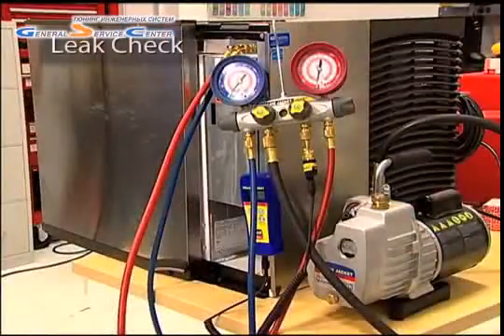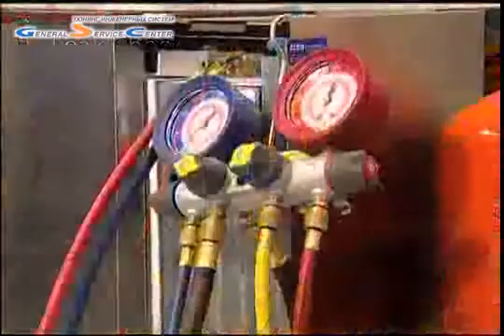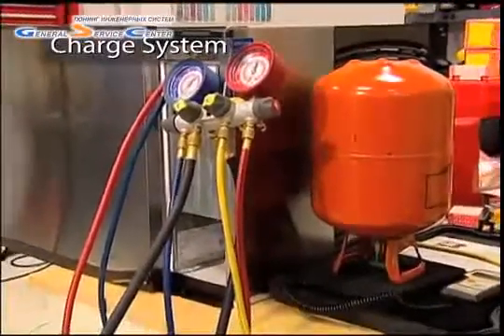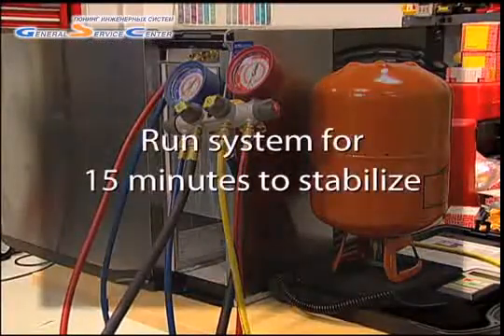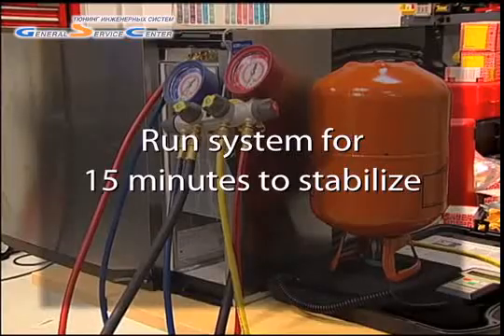Now with the TXV completely installed, perform a leak check on all connections. After ensuring that there are no leaks, you can properly charge the system to the manufacturer's requirements, making sure there is the correct amount of subcooling. Finally, let the system run for 15 minutes for stabilization before adjusting the superheat if necessary.